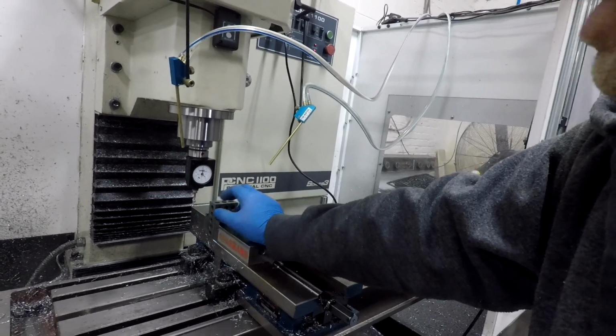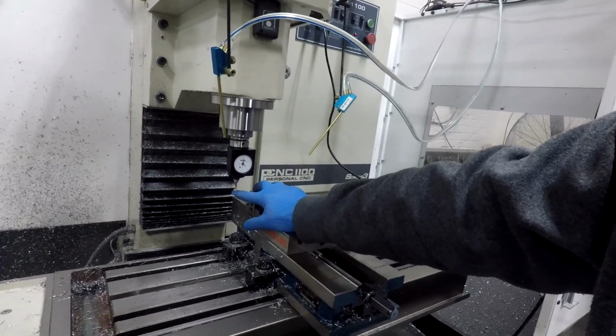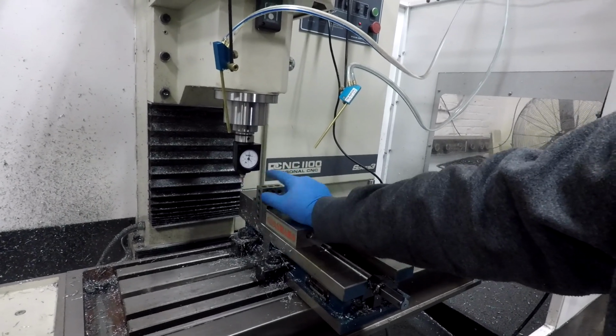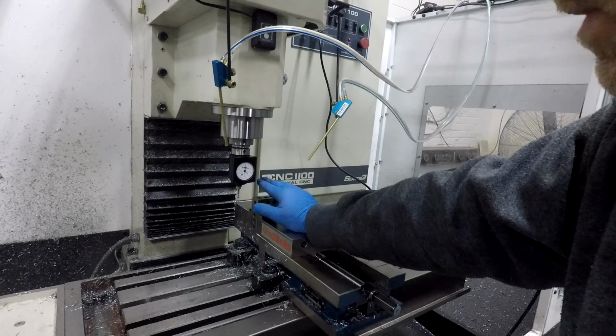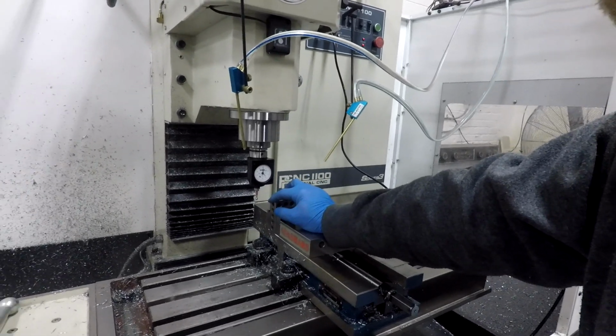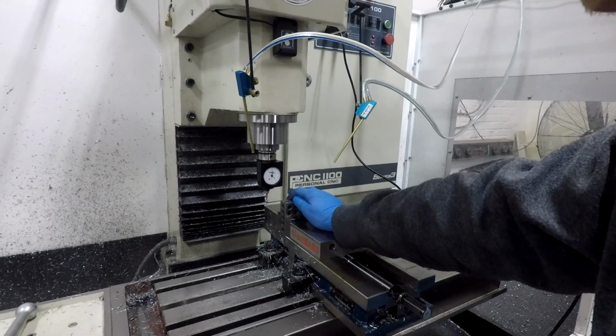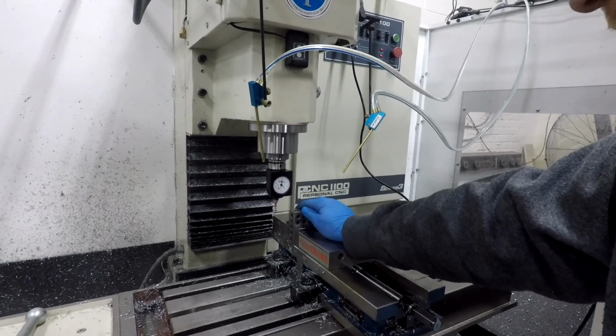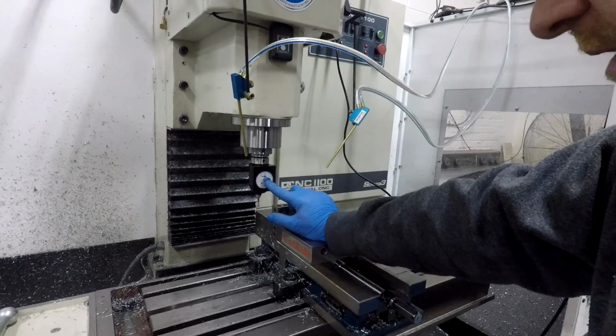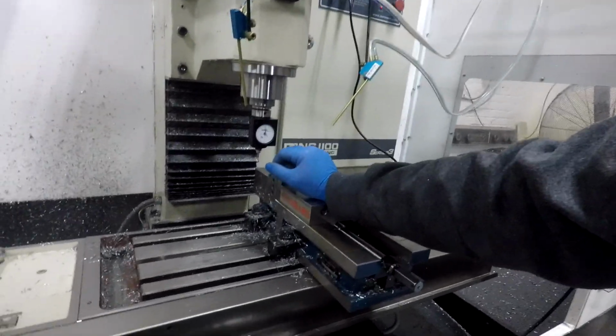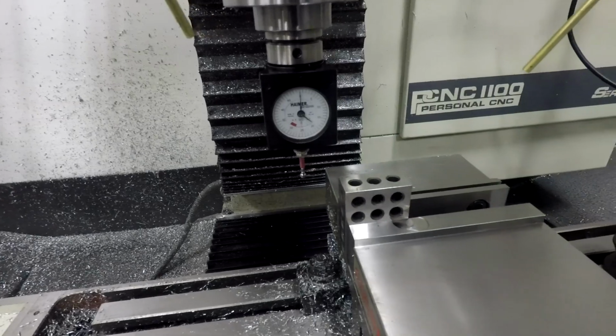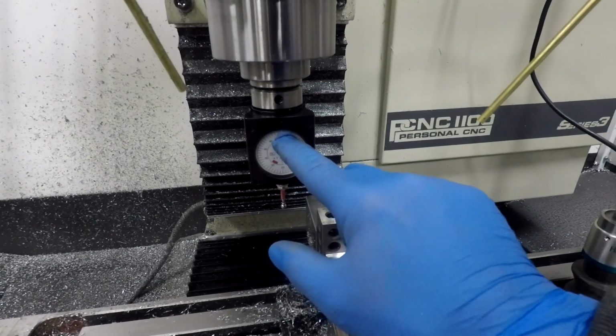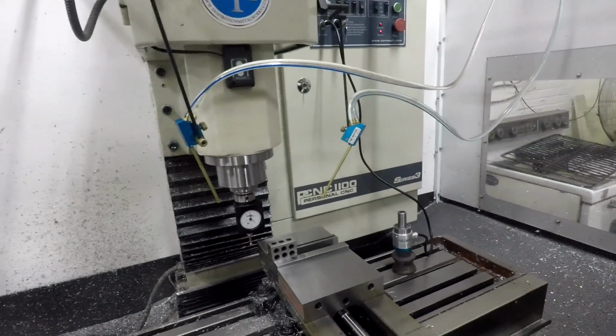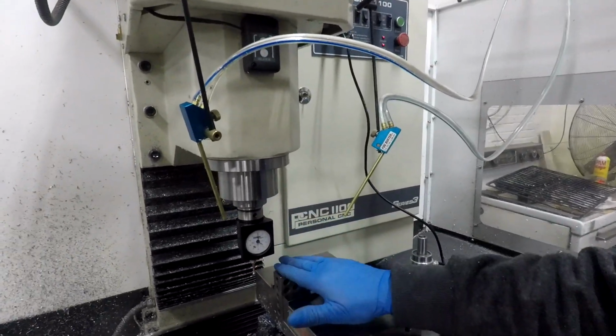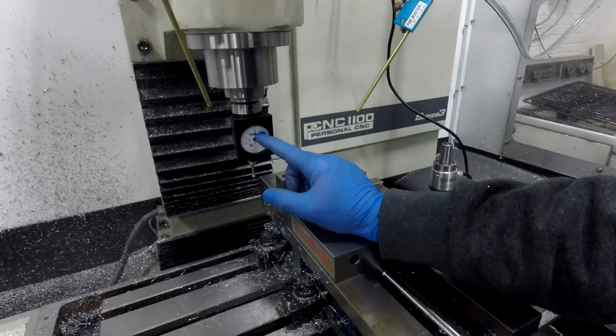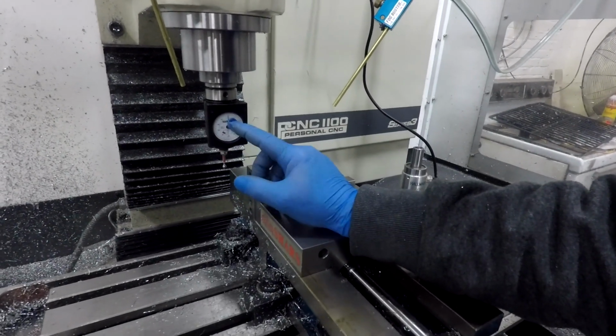Now when you go to your X and Y, you're just setting off the probe, so once you dial in the width of that probe and the offset of that, it should be relatively close. And the measurements that I got were X was spot on perfect and Y was off by half a micron, which, hey, you know, I'll take it. And that's with making sure that you have to dial this in, get that zero just perfect. And it's a little hard to do. It's much easier with the probe. The probe just touches off, senses it, and calibrates it. This kind of has a little bit of user error factored in.